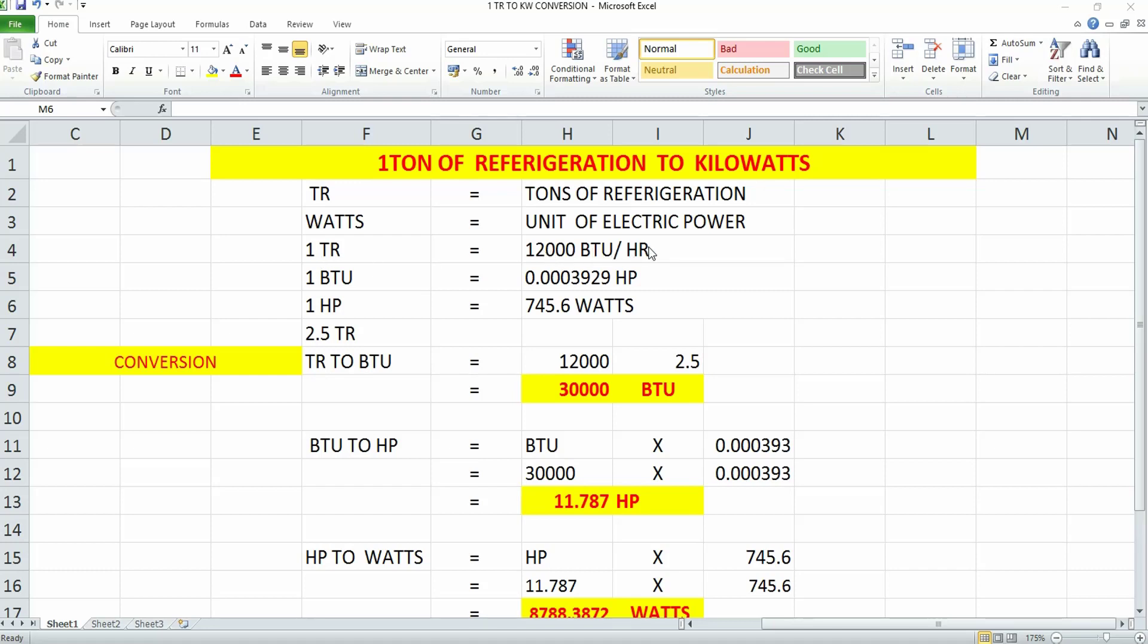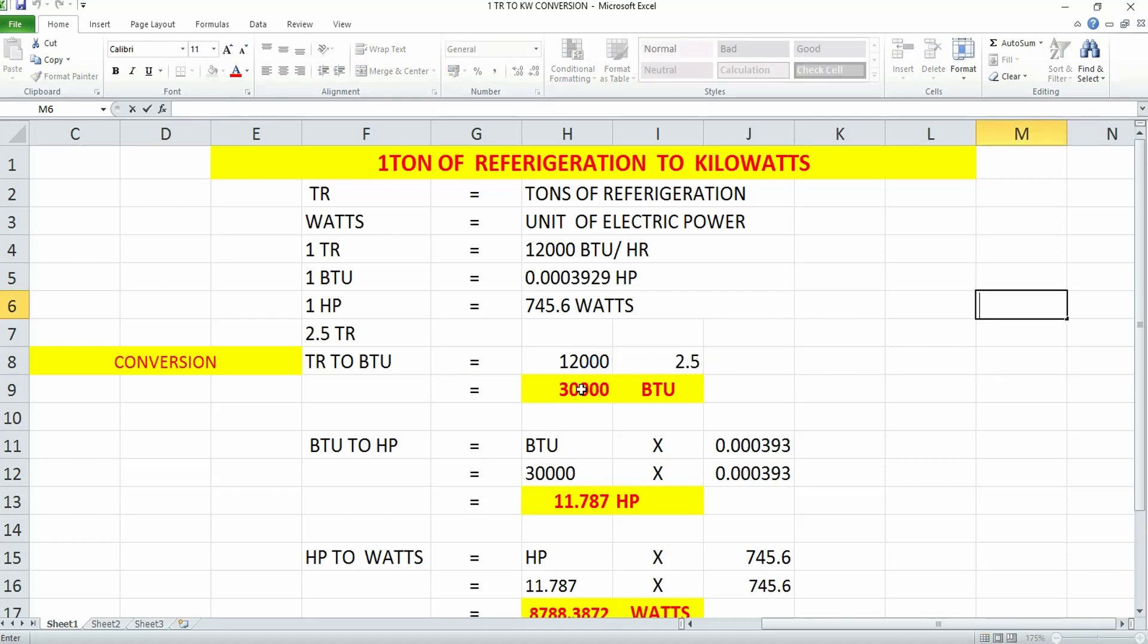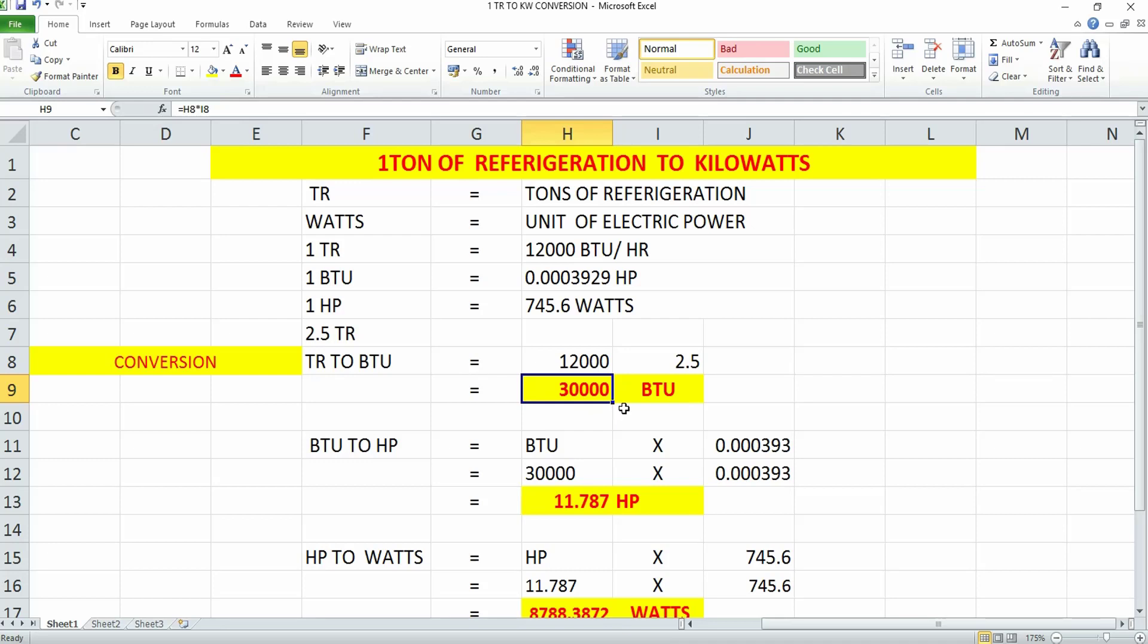I need to convert 2.5 TR to BTU, so I'll multiply 12,000 BTU by 2.5 TR, which gives 30,000 BTU per hour. Now you've converted your TR to BTU—2.5 TR equals 30,000 BTU.